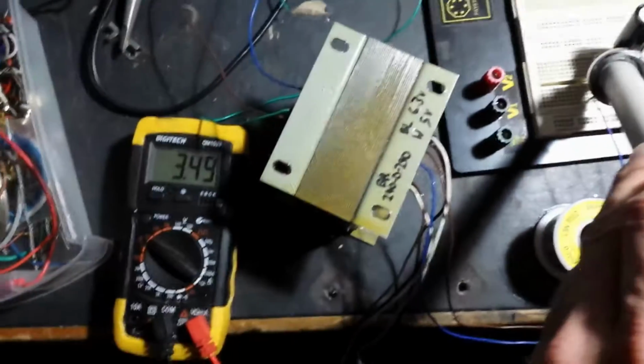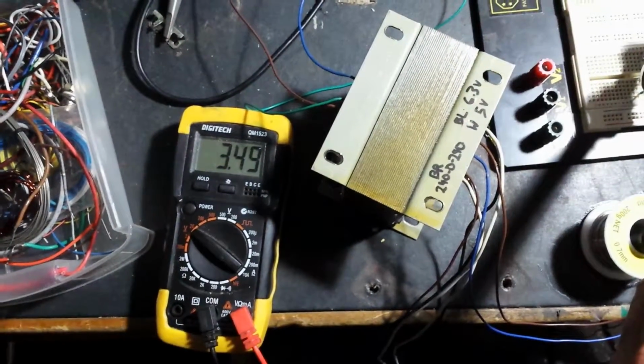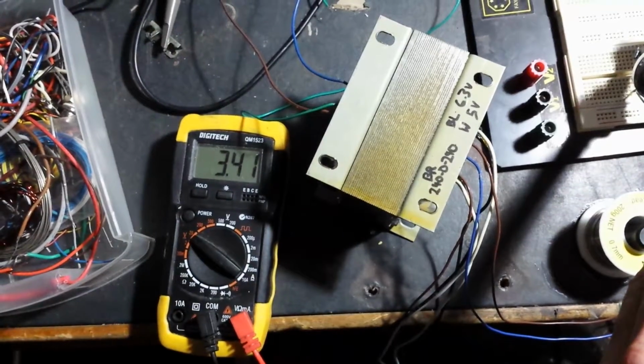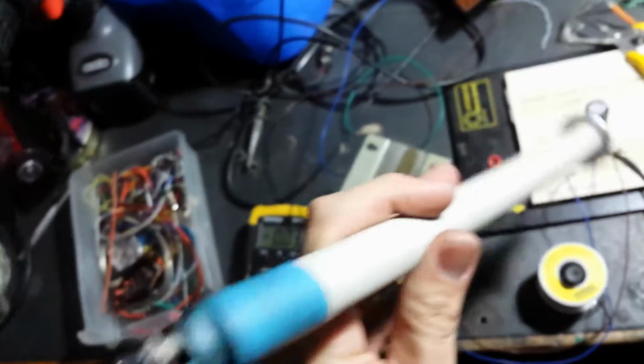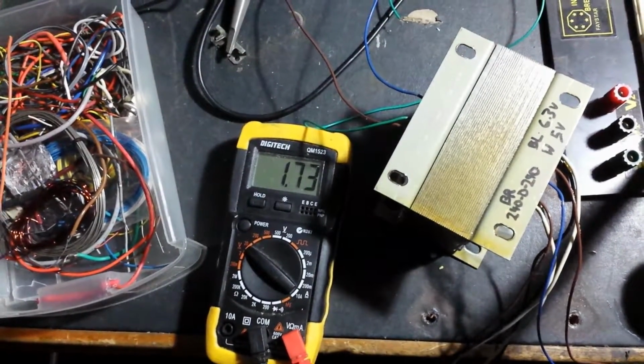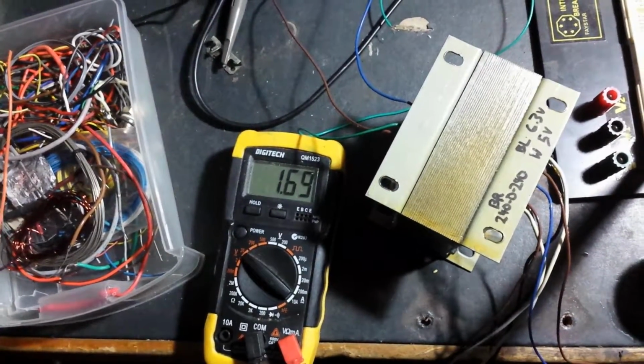Now I'm going to unplug the probe and plug in the high voltage probe, and I'm going to set the multimeter down to 20 volts, and I should get 3.4 to 3.55 volts from the high voltage probe. So I'll just put it on here. I'm getting about 3.4 to 3.5 volts, so it's reading quite accurately. And I'm going to set it to divide by 200, and I should get about 1.7 to 1.78 volts. Yeah, I'm getting pretty much close to that, so it is quite accurate.